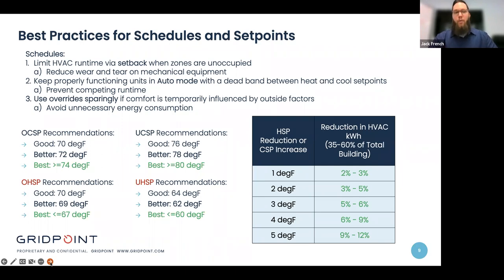And then what goes with schedules is, what do you use as your set point? Talking about the top two, I'll talk about occupied cooling set points and then unoccupied cooling set points. The recommendations for heat set points are just below those. So what we would recommend, assuming that you have properly functioning units in spaces, properly sized, and no known exceptions or no known compressor outages, things can respond the way that they are expected to respond. Good, better, best for occupied cooling set point would be 70 is good, 72 at better, 74 and above at best.